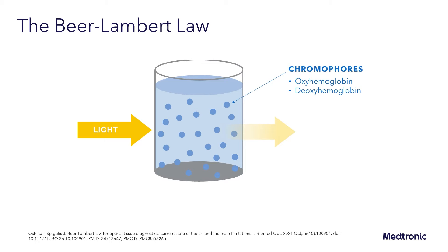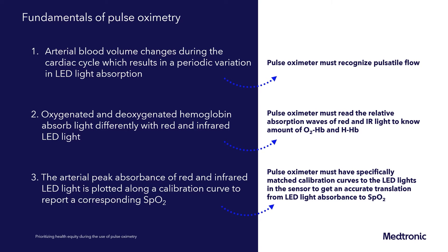There are three fundamentals of pulse oximetry which we'll discuss in detail as we move through the program. The first is that arterial blood volume changes during the cardiac cycle result in a periodic variation in the LED light absorption. The pulse oximeter must recognize pulsatile flow, or it's unable to measure oxygen saturation.